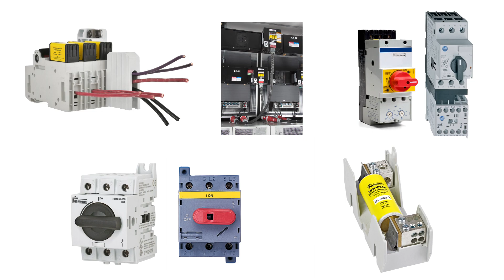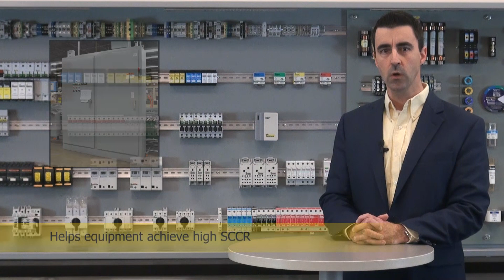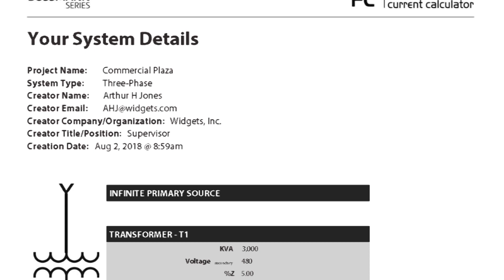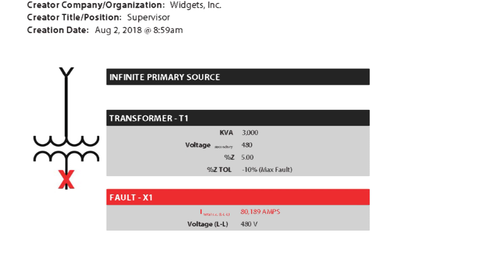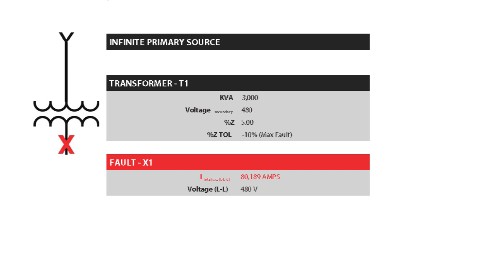Conductors, busway, motor starters, switches, and other devices can be well protected with current limiting fuses. Fuse current limitation helps equipment achieve high short circuit current ratings. Branch circuit components inside industrial control panels and machines, HVAC control panels, and other UL 508A listed equipment can be protected by current limiting fuses in the feeder circuit.